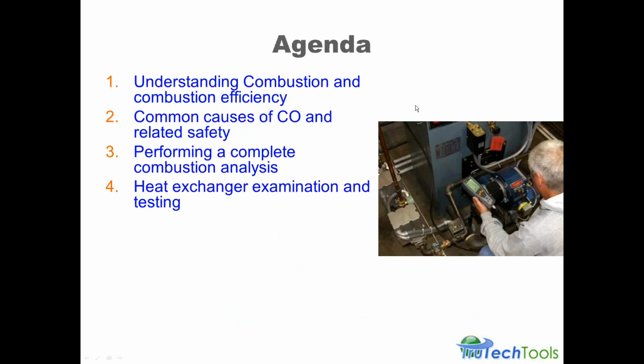So the real basic agenda today, we're going to try to convey and help you increase your understanding of combustion and combustion efficiency. We're going to look at some of the common causes of CO and CO safety issues, and also how to perform a complete combustion analysis with a digital combustion analyzer. And we'll also get a little bit into heat exchanger examination and testing, because heat exchangers with warm air furnaces and warm air heaters, some of the flue products getting into the distribution air side can cause some real issues for health and safety. So we do want to cover that important point.